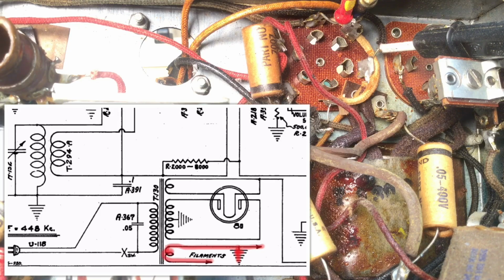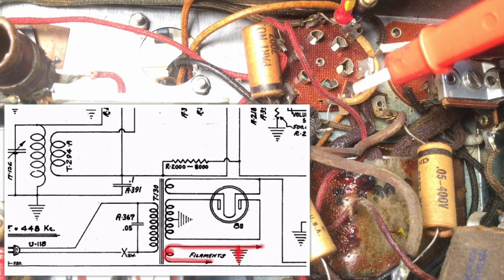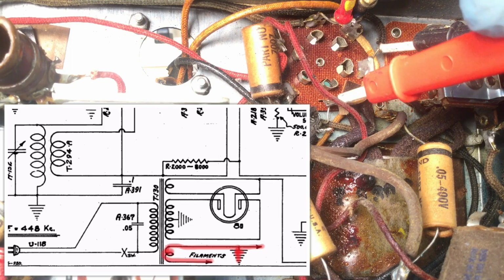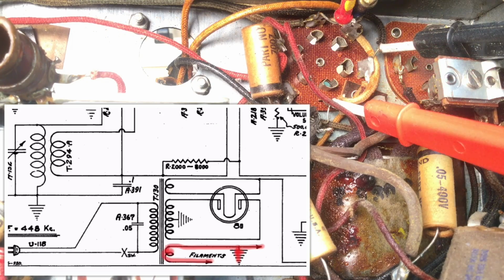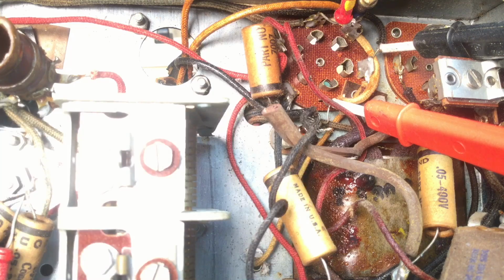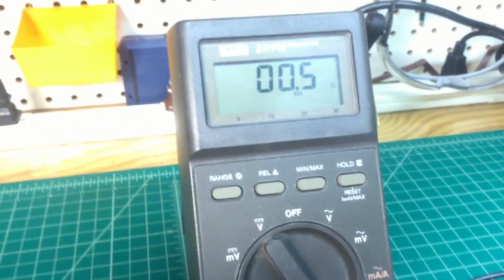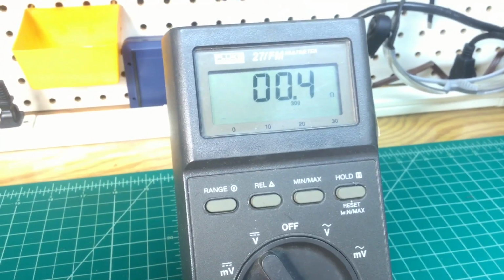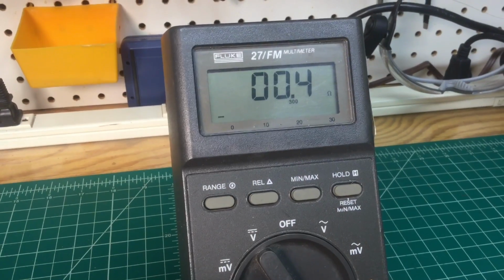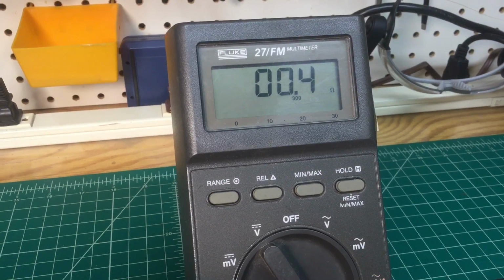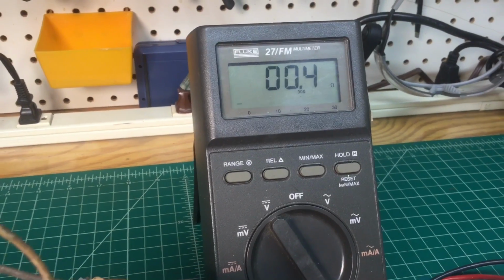So I'm just hooking up my test leads accordingly. And we'll do the same drill. I'll swing over and we'll take a look at the DC resistance on the meter and see what we get. I would think it would be just a bit higher than that 5 volt winding, maybe 0.3, 0.4, 0.5. And here we go, 0.4, 0.5 ohms of DC resistance. So just what I would expect to see on a transformer like this.